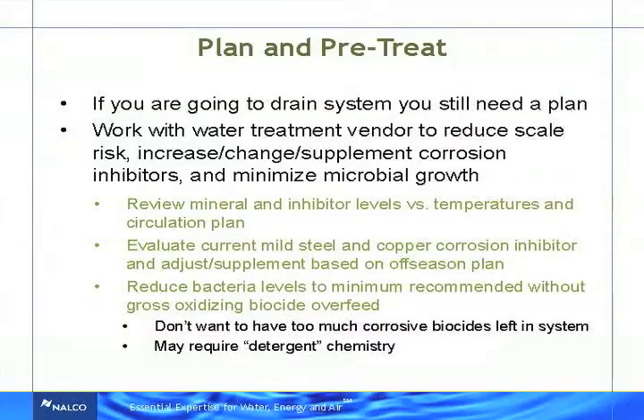The other thing you want to do, and this is the number one, is corrosion control. You're not going to get a lot of flow. We're going to talk a little bit more about that in a second, but if you're not going to get a lot of flow, what can you do corrosion-wise to prevent issues from occurring in that off-season? So work with your vendor. You might add more inhibitor. You might change the inhibitor you use, or you might try to increase circulation.